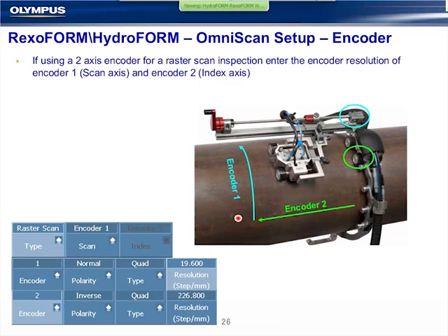And like I had said, now that customers are using this and acquiring a lot of experience, they are finding that they can map out a 60 millimeter stroke on the pipe, acquire a circumference of data, move the mapper without this axis, but do it manually, reset the encoder position, and build a C-scan with a surprising amount of precision, even without the two axes.